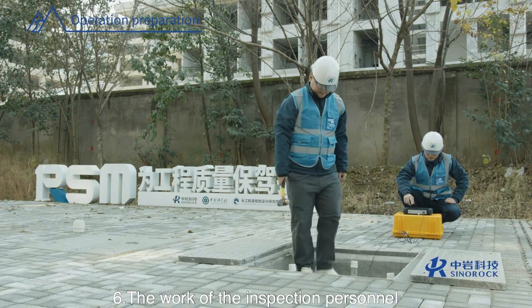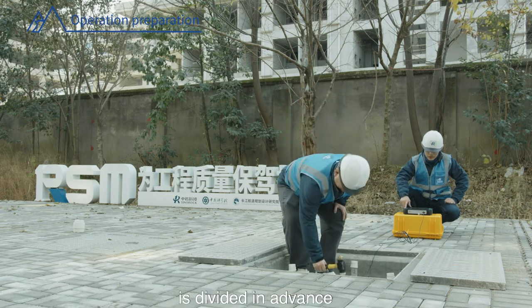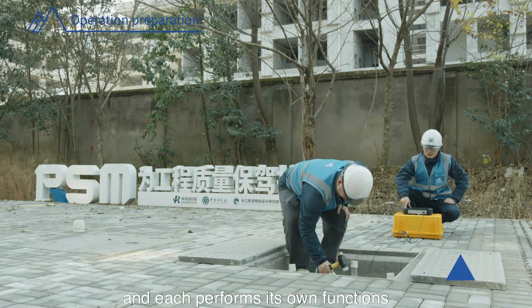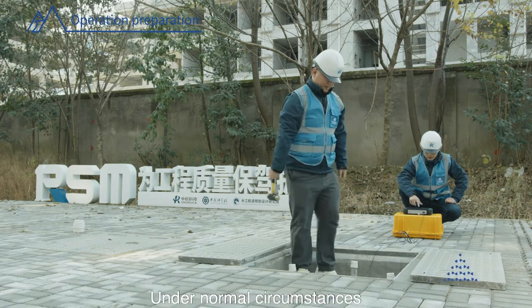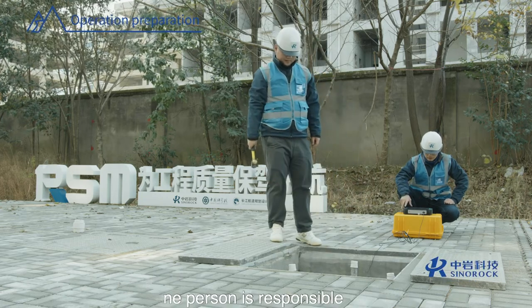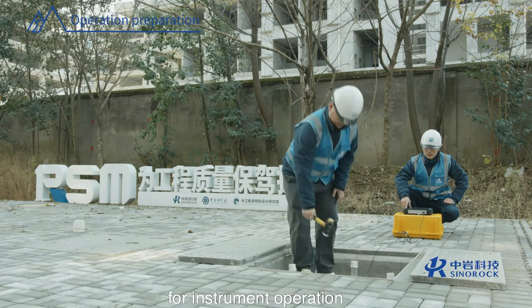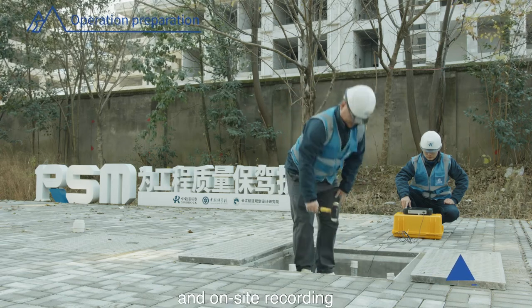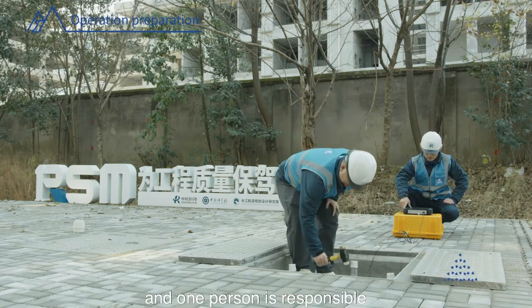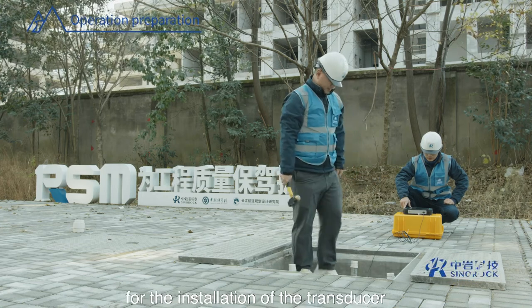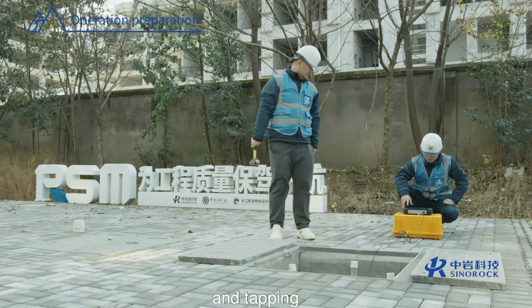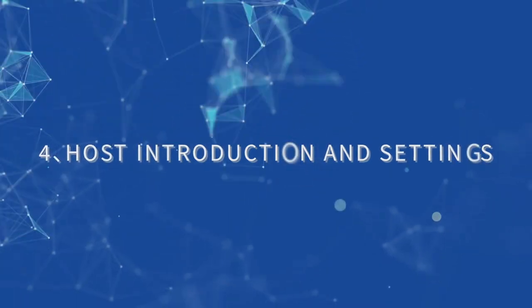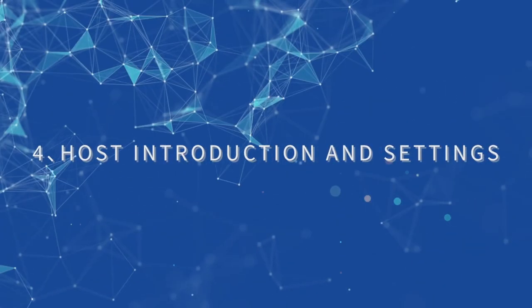6. The work of the inspection personnel is divided in advance, and each performs its own functions. Under normal circumstances, one person is responsible for instrument operation and on-site recording, and one person is responsible for the installation of the transducer and tapping. 4. Host introduction and settings.